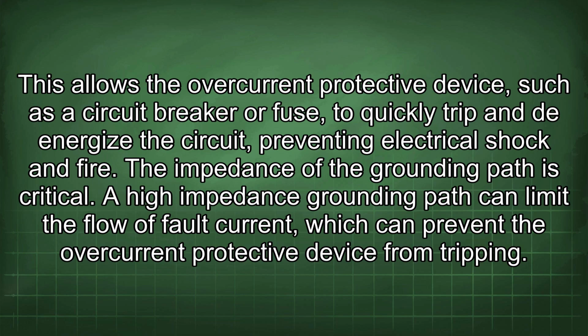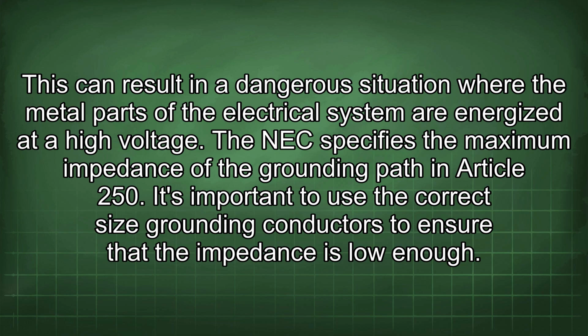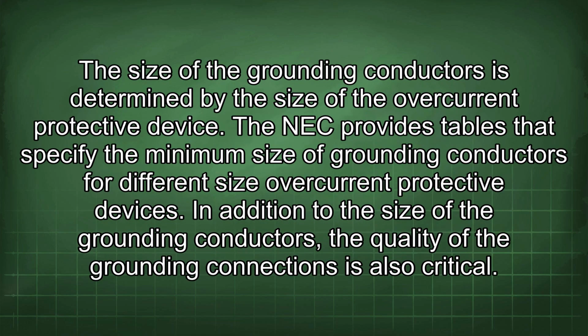The impedance of the grounding path is critical. A high impedance grounding path can limit the flow of fault current, which can prevent the overcurrent protective device from tripping. This can result in a dangerous situation where the metal parts of the electrical system are energized at a high voltage. The NEC specifies the maximum impedance of the grounding path in Article 250. It's important to use the correct size grounding conductors to ensure that the impedance is low enough. The size of the grounding conductors is determined by the size of the overcurrent protective device. The NEC provides tables that specify the minimum size of grounding conductors for different size overcurrent protective devices.